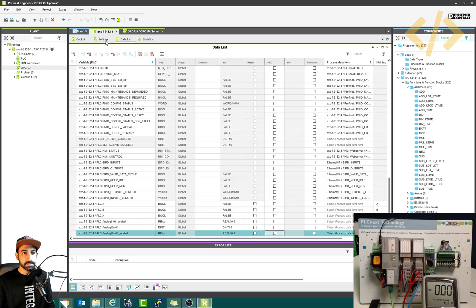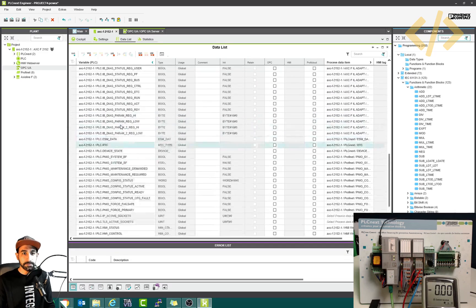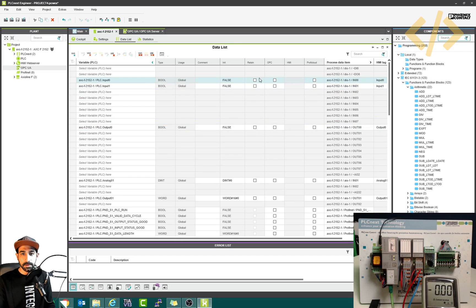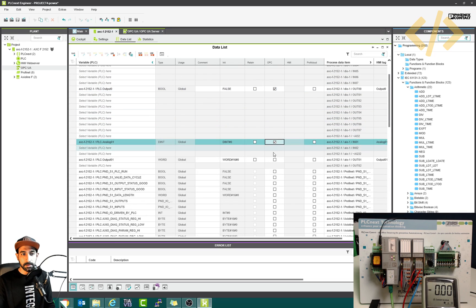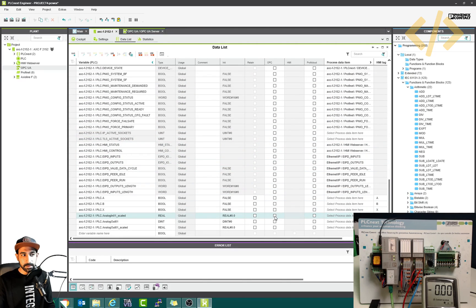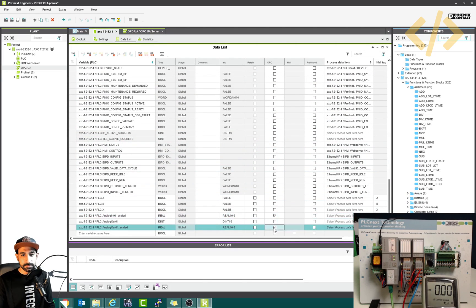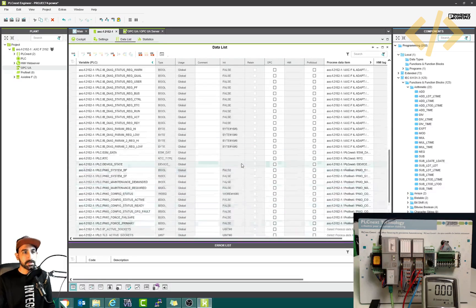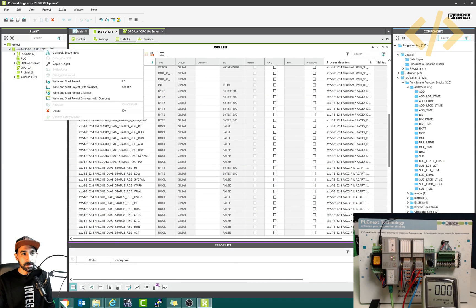You go to the PLC in the data list — these are all the variables. Let's see the variables we worked on in the last video. We have input zero — I will tick this — input one, output zero, analog input/output. Going down, I see some scaled tags and variables a, b, and x. These are the tags I want to monitor on my OPC UA client. Once you define the tags and enable OPC UA with the IP address, just download that.